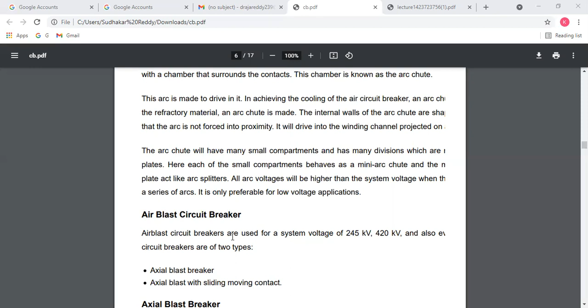Now the second one is air blast circuit breakers. Air blast circuit breakers are used for system voltages up to 245 kV, 420 kV, and even higher. There are also two types of these circuit breakers: axial blast, and axial blast with sliding moving contact. First of all, let's discuss axial blast breakers.